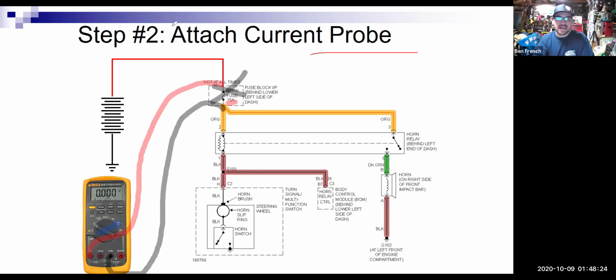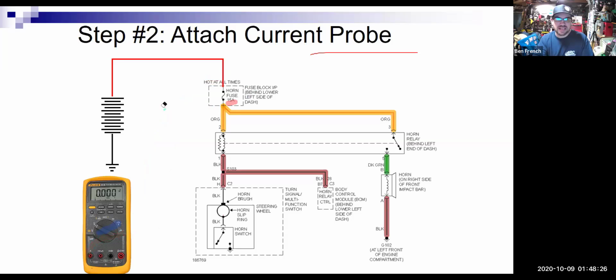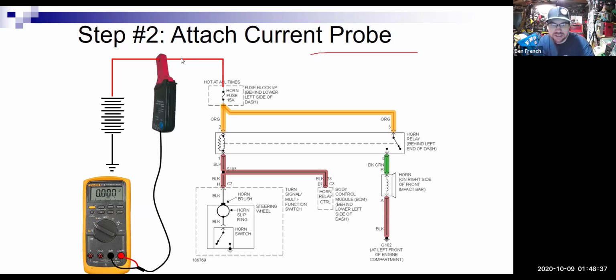So the reason that in this example, instead of hooking the meter up in series, I'm attaching a current probe is it's a little safer. You're not going to risk damaging your meter or blowing the fuse if you use a low current probe. But you could test this directly by measuring the amperage through the circuit, because remember, what does the work? It's the amperage. So you've got to make some decisions based on what you measure there.